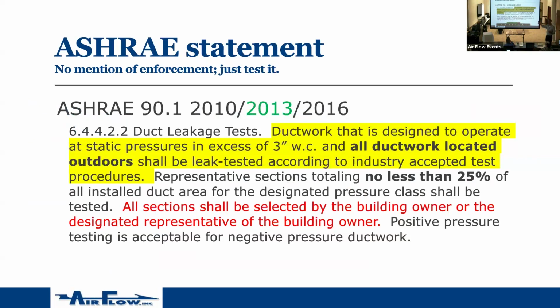Representative section. So what this is saying, if you're seeing me point, no less than 25% of the ductwork inside the building is supposed to be tested. I have a hard time imagining that actually takes place. I've heard of systems in hospitals going completely untested. Oops, the insulator already insulated it, it's too late. All sorts of stuff like that. It is supposed to be tested.